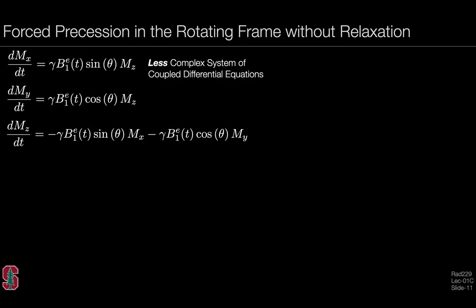To design the fastest hard RF pulse, we typically want short pulses for time efficiency. We start by specifying the flip angle — for example, pi over 2 or 90 degrees — then use the maximum available B1 of the system, typically on the order of tens of microtesla, to find the shortest possible pulse duration. Rearranging the flip angle expression, with a flip angle of pi over 2, the appropriate gyromagnetic ratio, and a B1-max of 25 microtesla, the RF pulse would be approximately 235 microseconds in duration — quite short to tip the magnetization a full 90 degrees.